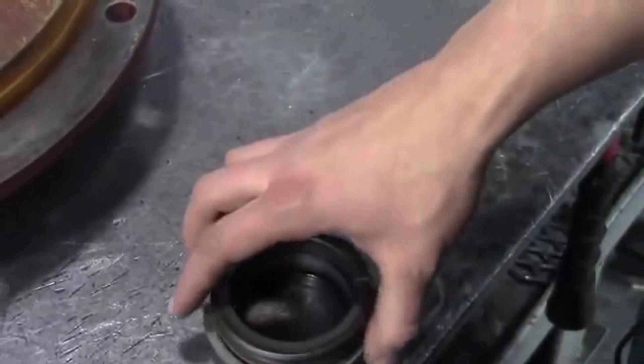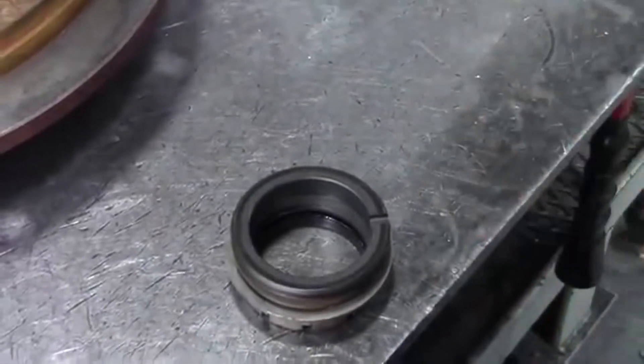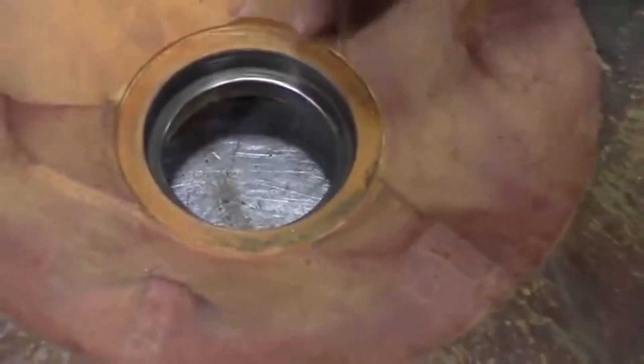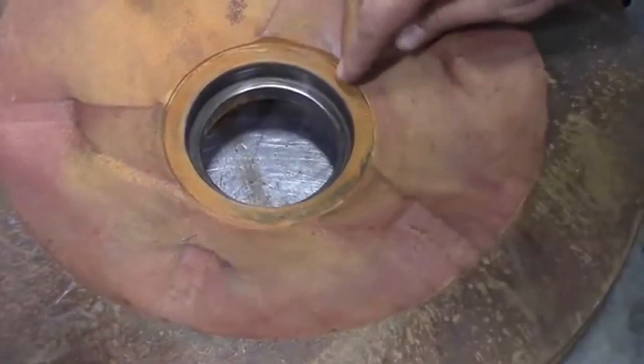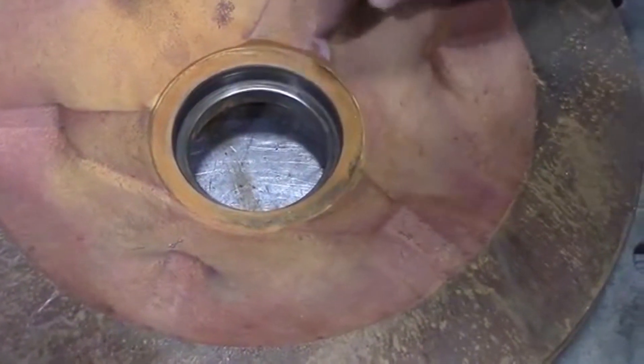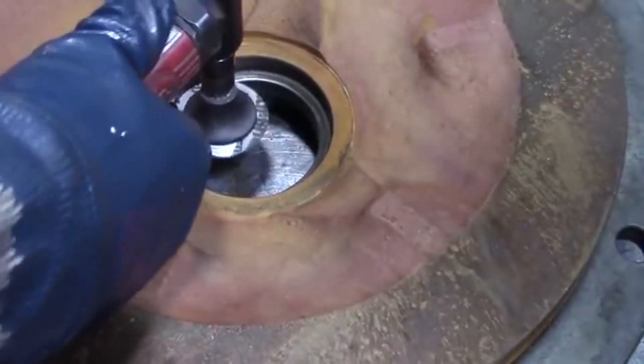Do you suggest, just for safety's sake and reliability, just not reusing it? Yeah. When you're going back together, pumpage stuff can build up around the edge of the stationary seat. So you want to make sure to clean this bore back up before you put your seal back together, so you can make sure it goes in evenly and you don't get anything on the faces.